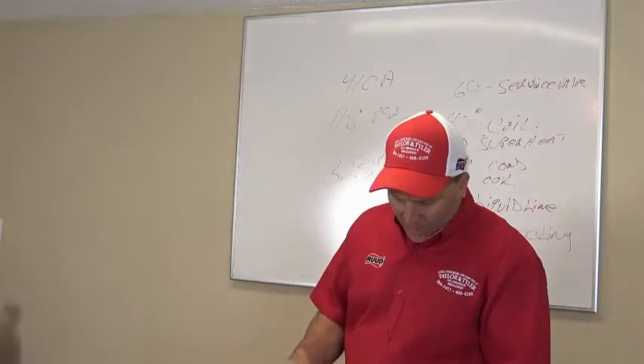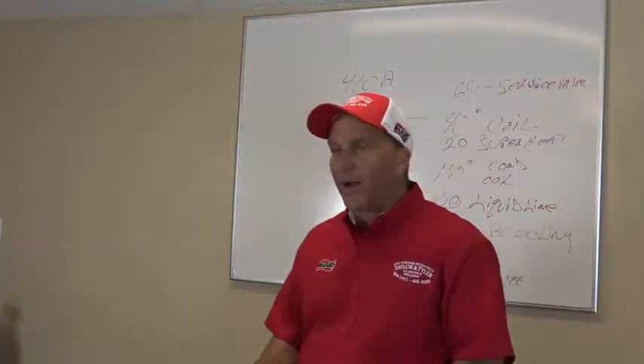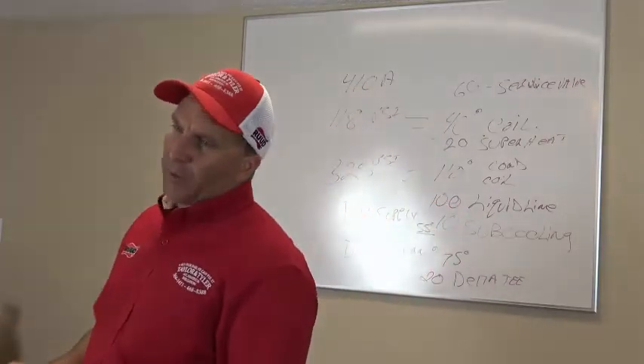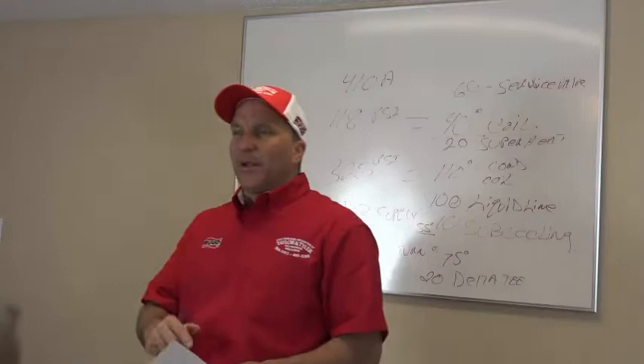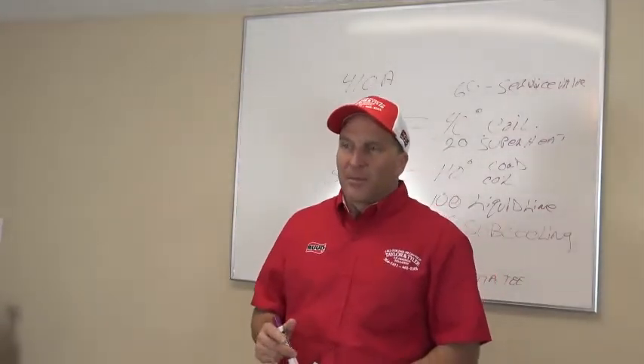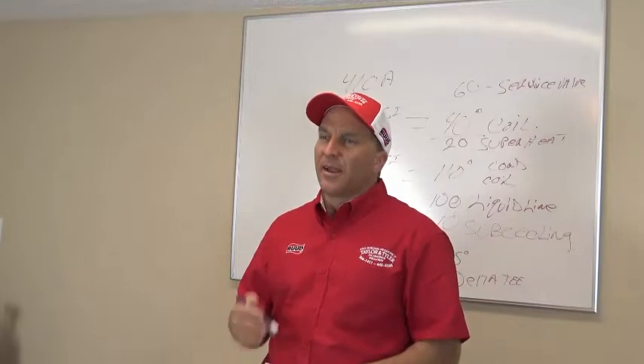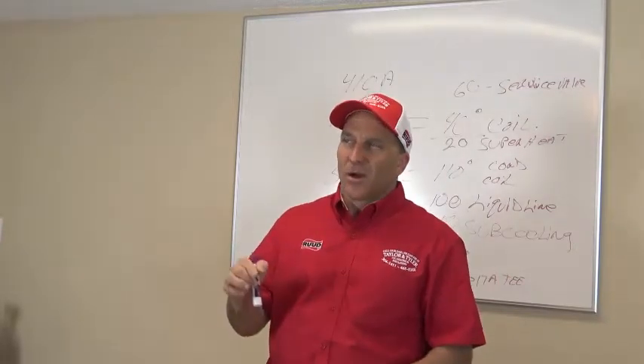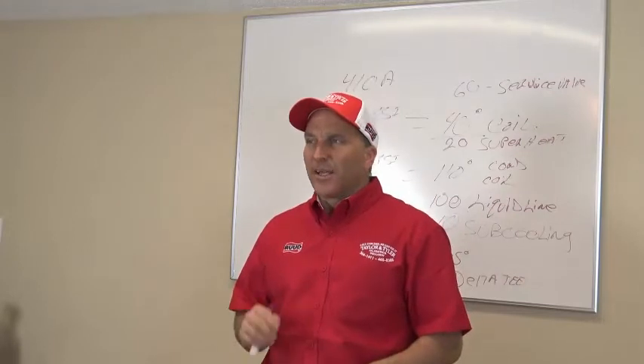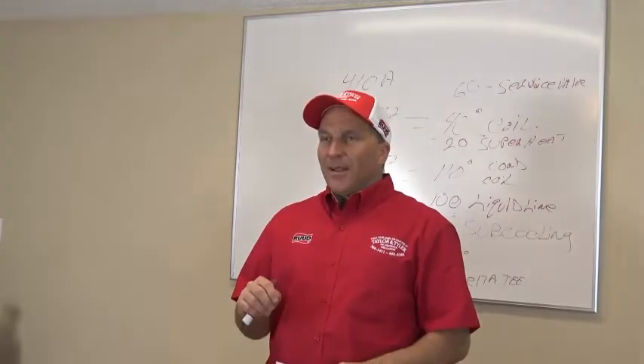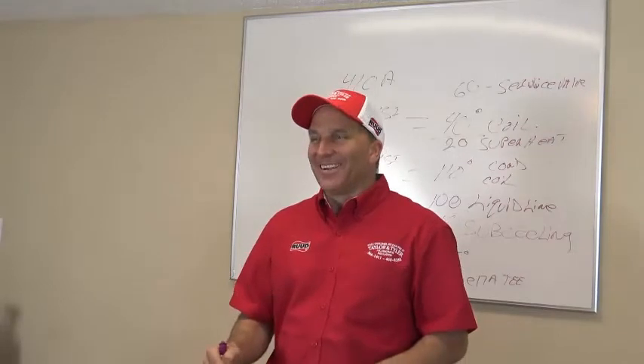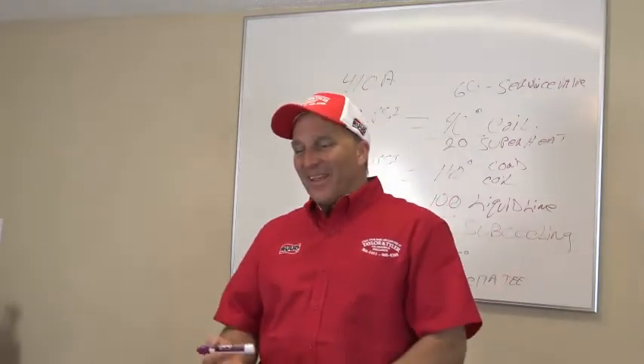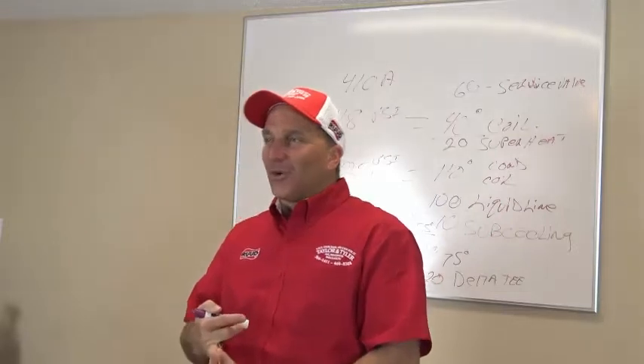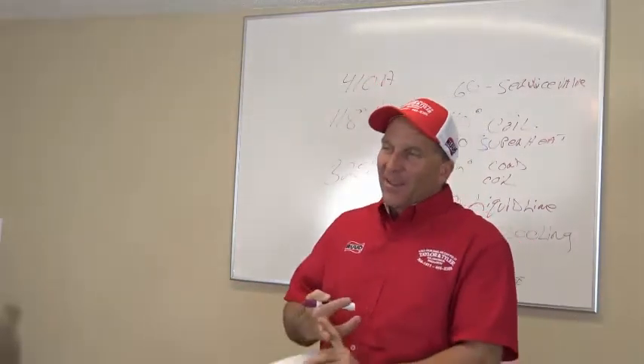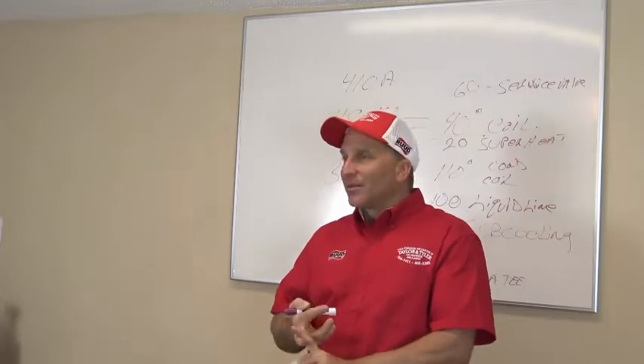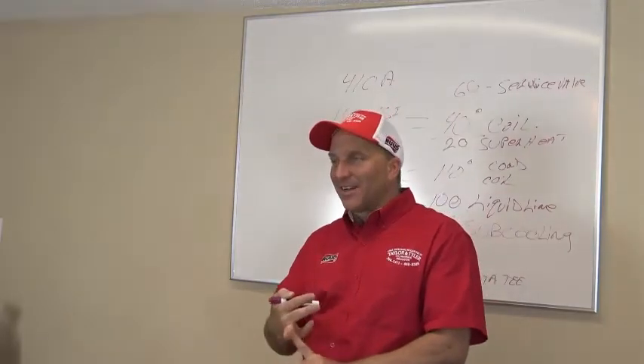Wiring on the system. Is the wiring burned or is it miswired? Well, if you get there and the system's running, it's probably not miswired. Probably not. But I'm going to tell you what, I just went to a friend of mine's house the other day, had a 2-stage air conditioning system that was installed right after Katrina. It has never worked on second stage. He had a single-stage thermostat. The Y2 was not even hooked up in the condenser. The W2 was never hooked up, so he never had second-stage heat, never had second-stage air conditioning.